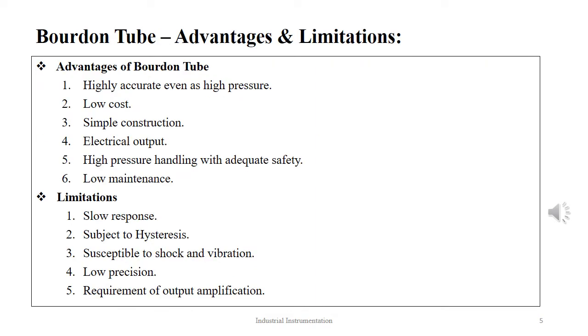The advantages of the Bourdon tubes are that they are capable of producing very accurate results. The tube is low on cost and simple in construction. The output can be read out as electrical signals. They are capable of measuring very high pressure with adequate operator safety. The results are highly accurate even at very high pressure. The Bourdon tubes are low maintenance devices.